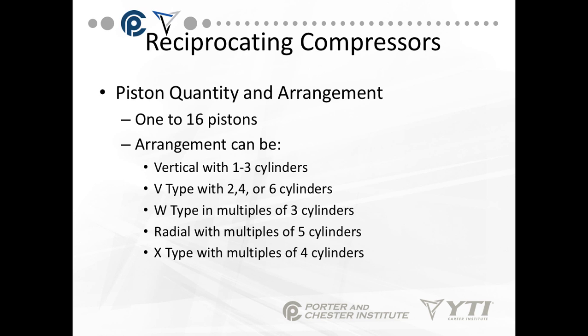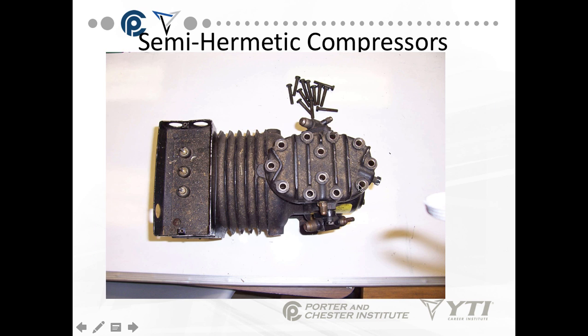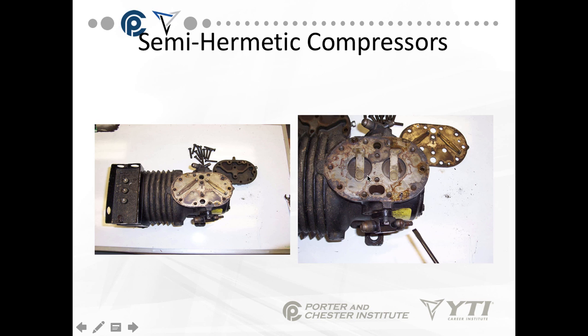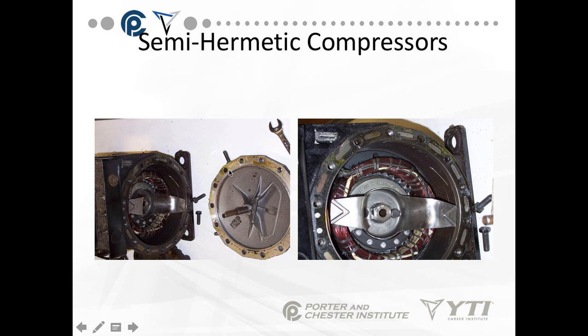Pistons in reciprocating compressors can range from 1 to 16. The arrangement can be vertical with 1 to 3 cylinders, V-type with 2, 4, or 6, W-type in multiples of 3, radials in multiples of 5, or X-type in multiples of 4. This is an example of a semi-hermetic compressor on a shop bench — you'll see it's all bolted together, with start components and wiring connecting over here. Taking the bolts off the cover and popping it off, you can see your valves and pistons. The valves are under the cover. Taking the front off, you can see the end of the motor with a splash-type lubricating system — two blades that circulate down to the bottom, pick up oil, and splash it across the bearings.